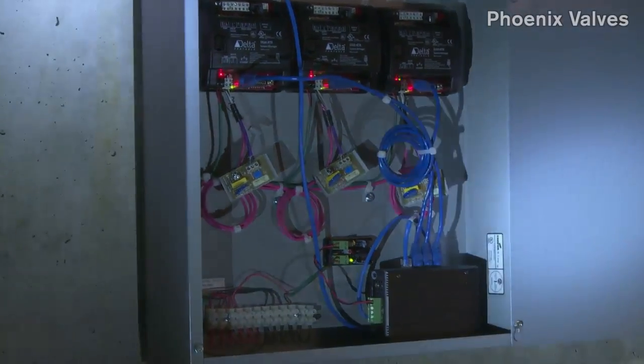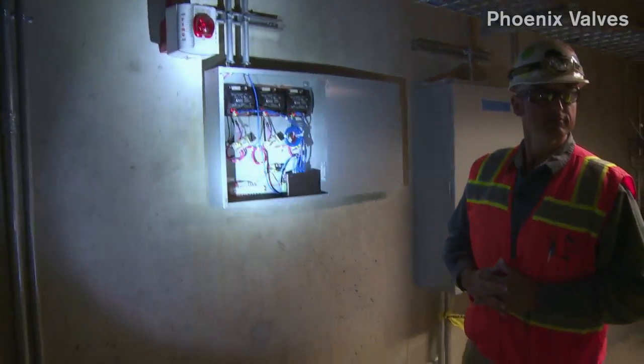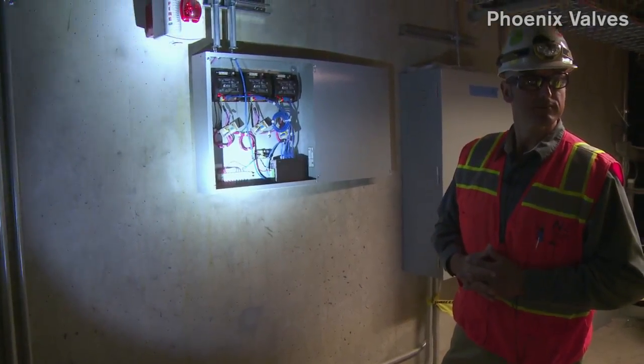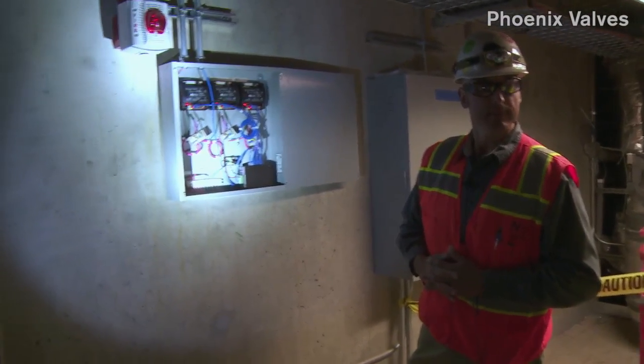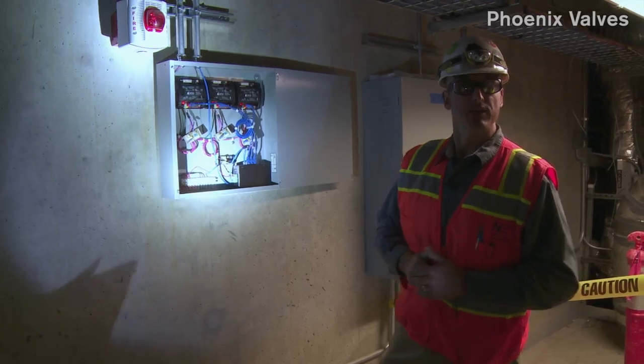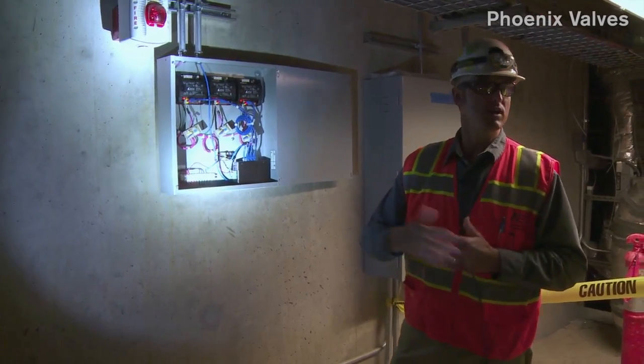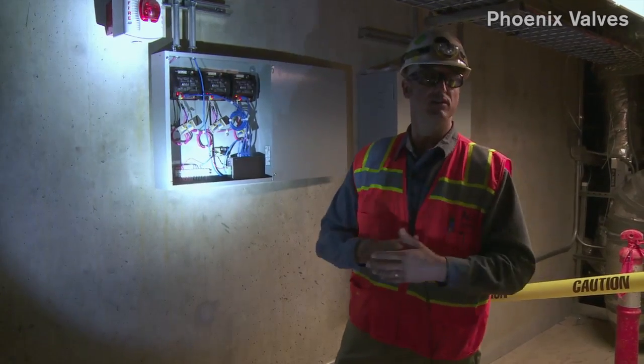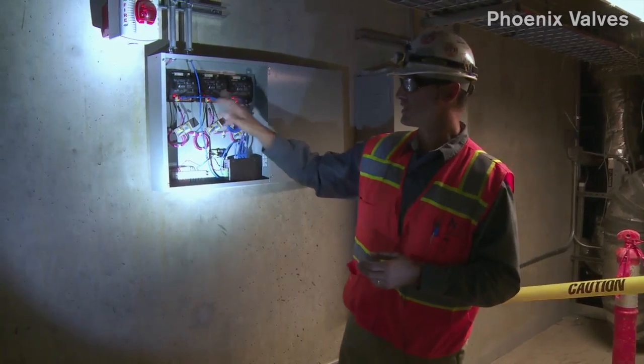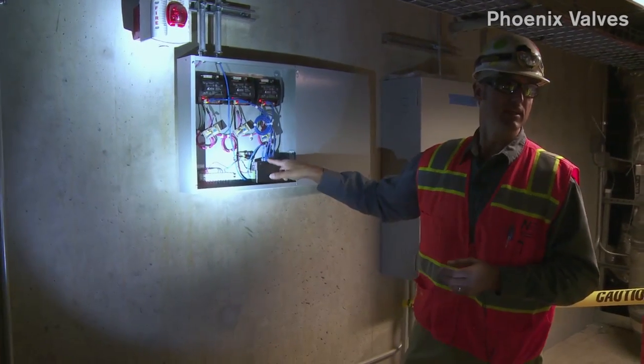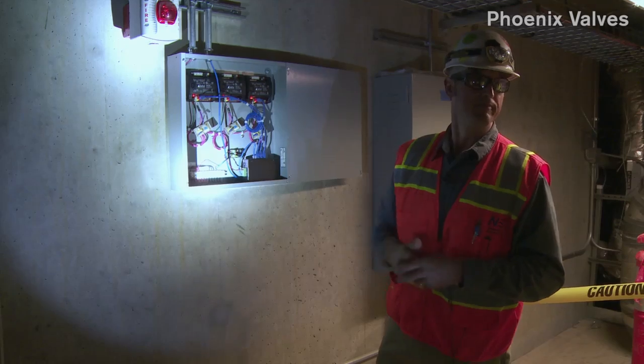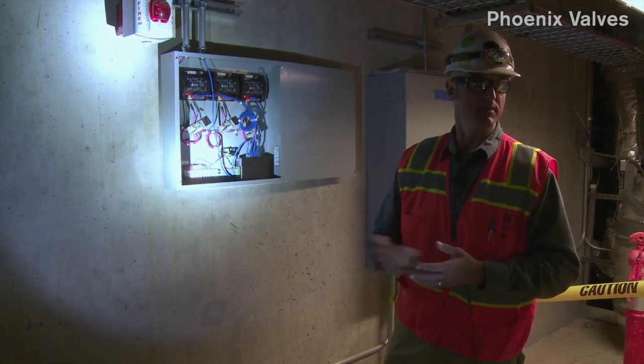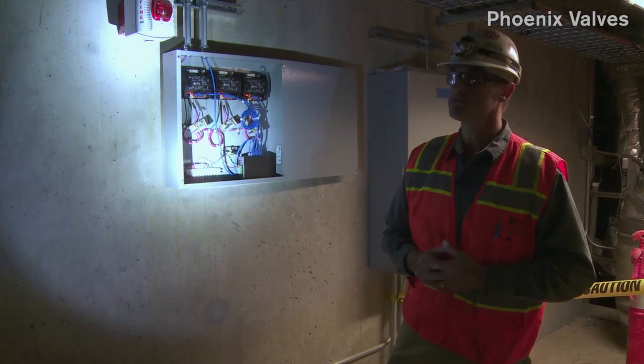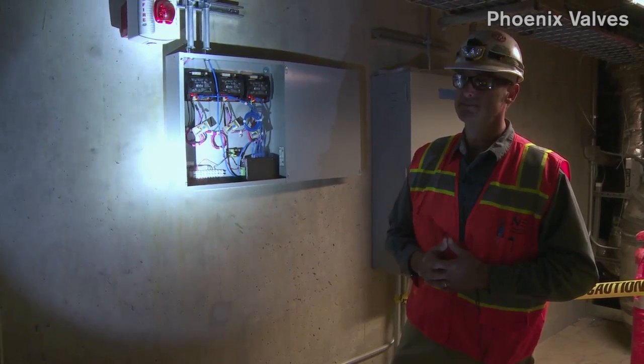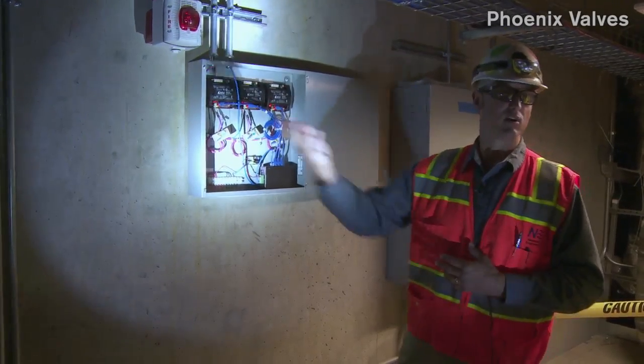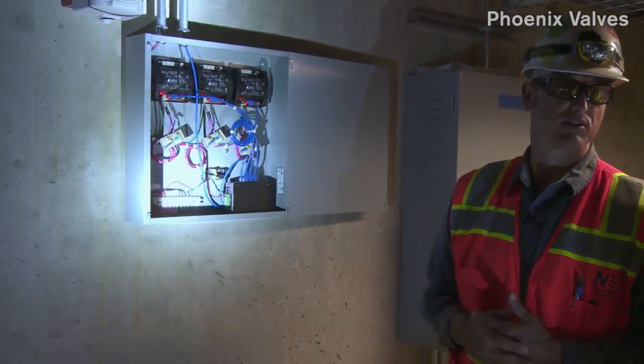For alarms, those general alarms, what if you have a bad valve pod or a bad actuator? Is that going to be seen on the front end of Johnson Controls? How will that alarm? If you have a bad actuator, say it's being told to go to 500 and you hit the switch, you want it to go down to 300, if it does not move, the signal goes through here and Johnson's picking it up, not through a hardwire, but just through the comm. So they're monitoring alarms, flow alarms, jam alarms. Okay. That would be a jam alarm. That'll come up as a jam, what we call command feedback mismatch. Right. And the fume hoods, it'd be a local alarm, and then it should actually go through your Johnson Controls system too.